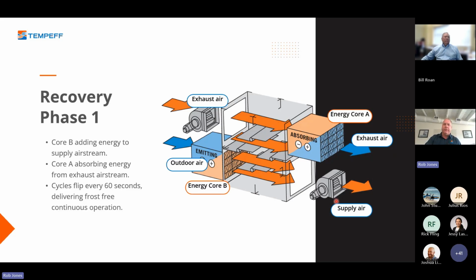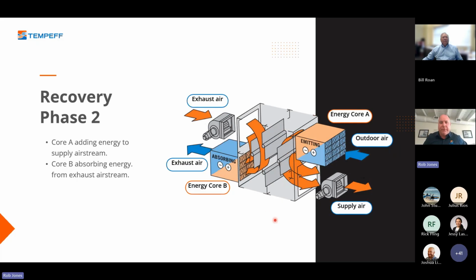That is when our units are the most efficient, at 60 seconds, and it guarantees us that we can maintain cross leakage at 1 to 3%, which covers the first 3 classes of air for ASHRAE 62. After 60 seconds, the damper will flip and is now in a vertical arrangement. You can see the exhaust air is now doing a U-turn and going through energy core B. Energy core B is now recharging. Over on the other side, the outdoor air is now shifted and coming through energy core A before doing a U-turn to the supply air and into the building.